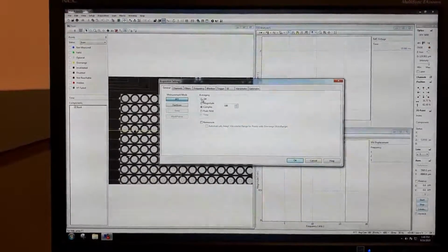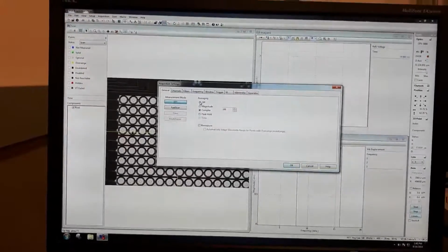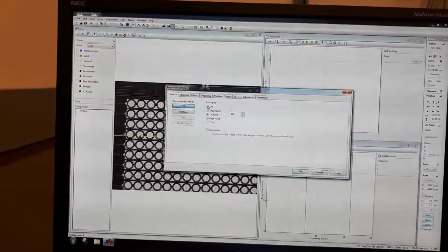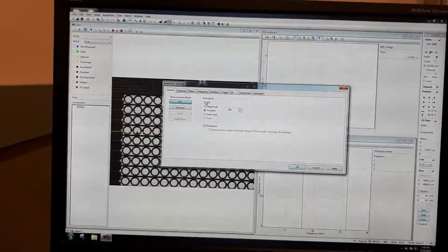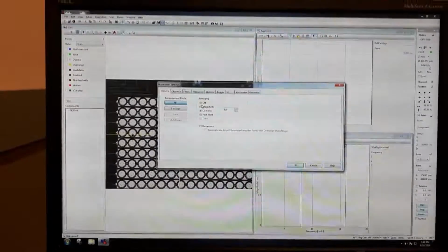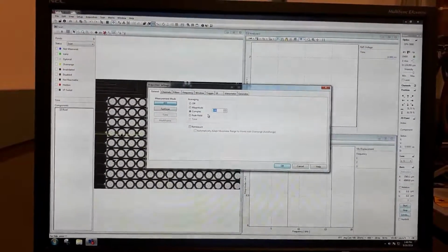Depending on the type of measurement you're doing, you might want to have averaging of your signal. Averaging of your signal will decrease the background noise, but it'll take longer. If you are measuring in the kilohertz range, the time it'll take to measure will be greatly affected by that. But if you're working in the megahertz, it's not that problematic. So I normally do complex, and I start with 10.